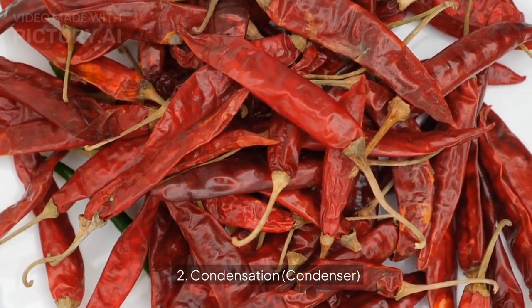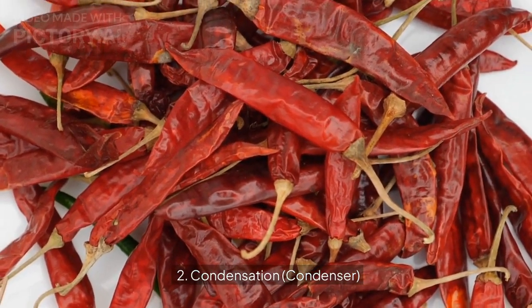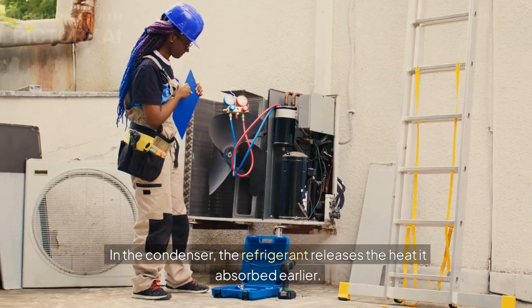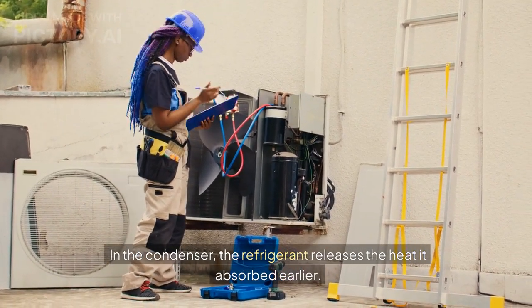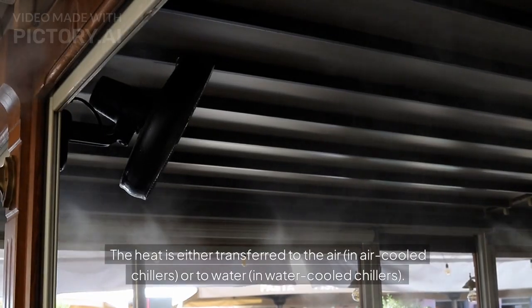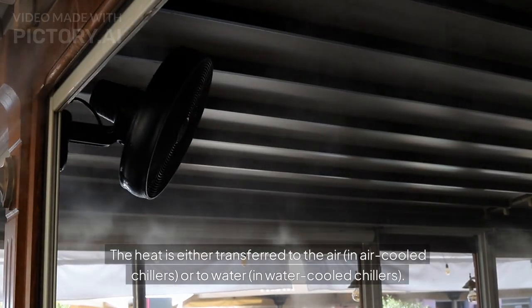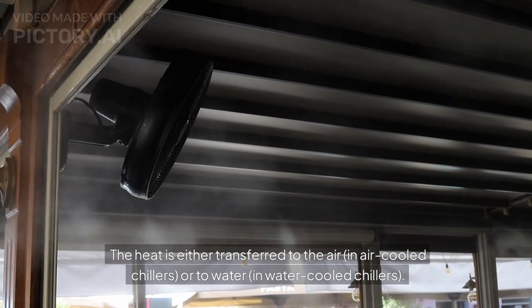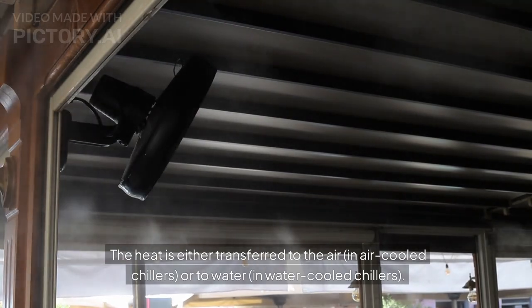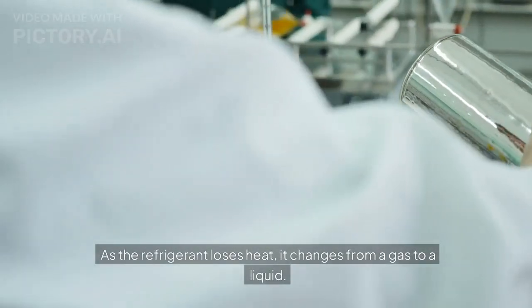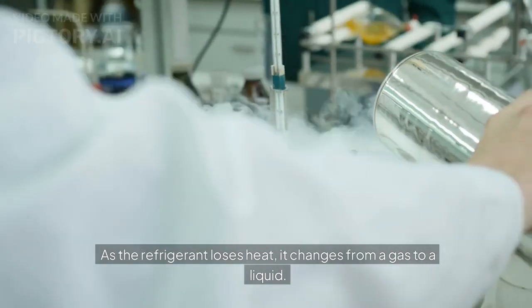2. Condensation. Condenser. In the condenser, the refrigerant releases the heat it absorbed earlier. The heat is either transferred to the air in air-cooled chillers or to water in water-cooled chillers. As the refrigerant loses heat, it changes from a gas to a liquid.